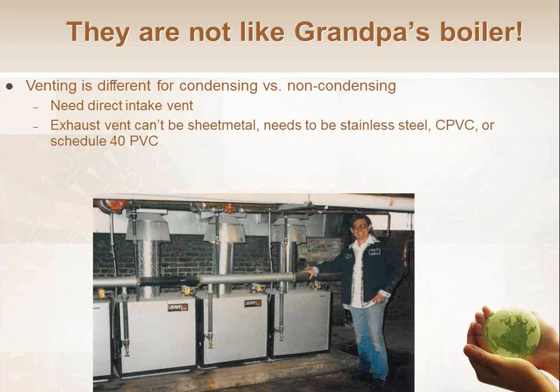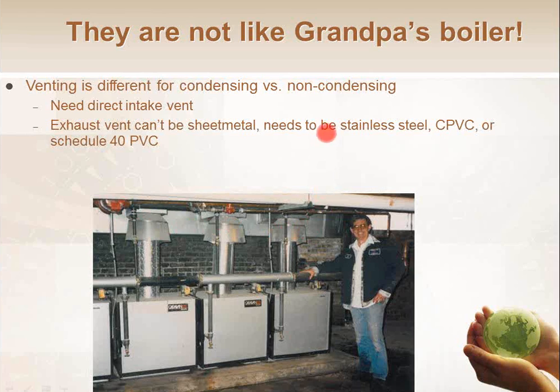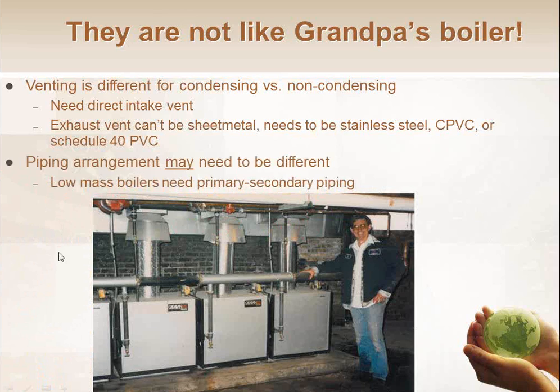So you will have to do some work on the venting when you change from an old to a new style boiler plant. You're going to have to switch from sheet metal to PVC venting, and you're probably going to have to get everybody a dedicated venting pipe. As you can see here, these 4 boilers, they're all dumping into that common plenum back there, and that's exhausting straight up. That will no longer work when you switch to the condensing boilers. The other thing that might change is, depending on the type of condensing boiler you use, you may have to do a little bit of piping work.